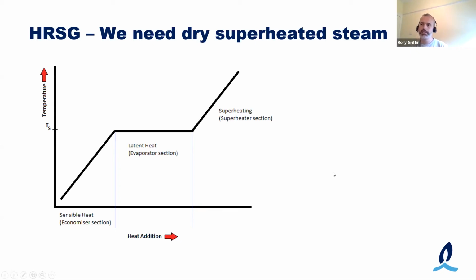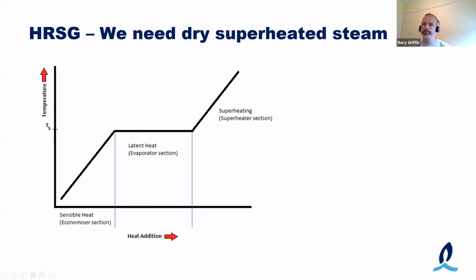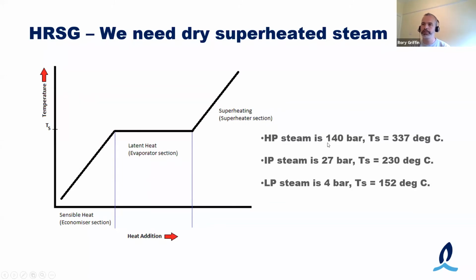So looking at the temperature profile, you have 650 degrees at the GT exhaust, and you can look up your steam tables. I hadn't seen steam tables probably since college, before I started this role in 2014. And if you look up the steam tables, what you'll find is for high pressure steam, saturation temperature over here is 337 degrees Celsius. For intermediate pressure steam at 27 bar, it's 230 degrees. And at low pressure, 4 bar, you're at 152 degrees.